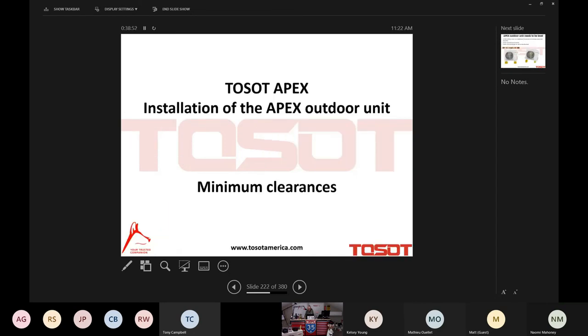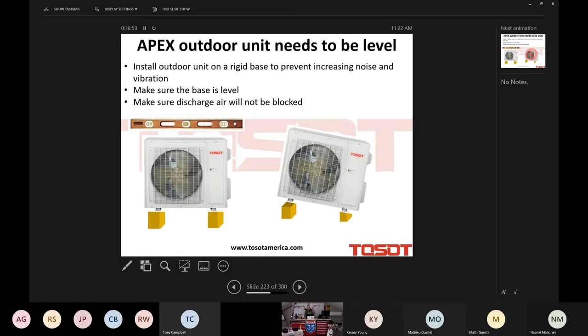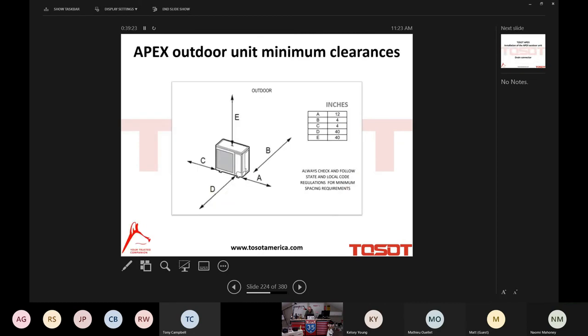Okay, guys, we installed the indoor unit. Let's look at the outdoor unit. I think we can move along at a pretty good pace here. I always ask our installers, can I ask one favor? I've been talking now for, what, 2.5 hours. I think I've earned a favor. Can we have the outdoor unit be level for 1 hour? That's all I ask, 1 hour. After that, I recognize it's out of our hands. God takes over, right? The soil levels, nothing we can do about that. But for 1 hour, we could put a level on it and have that outdoor unit be level.